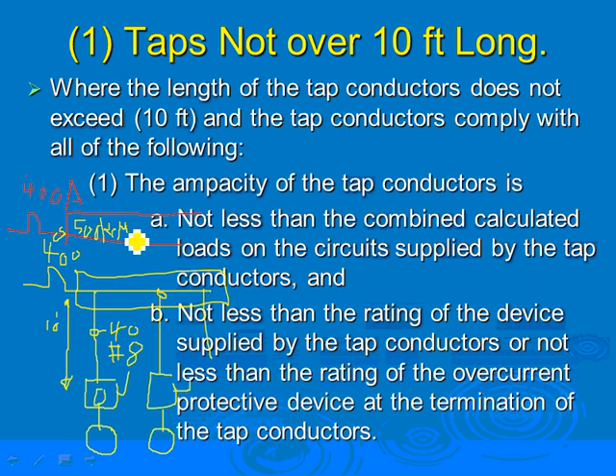Okay, so anybody disagree that a 400 amp circuit breaker or fuse can feed a 500 kcmil? I'm tapping the 500 kcmil into a number 8 conductor, right? Why number 8? Because you can't tap less than that. Can I tap number 12? No. Can I tap number 4? That minimum is number 8. And the only condition, guys, is here. Let's make it easy and use a fuse as the overcurrent protection device. What size fuse can I put right here? The maximum size fuse that acts as overload and short circuit protection here is 40 amps.